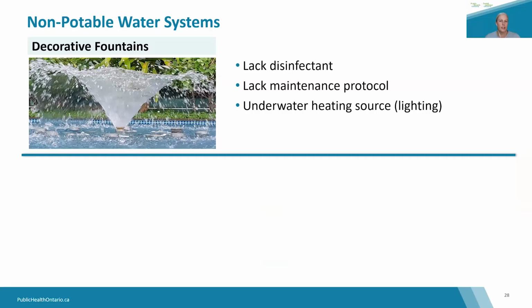So our non-potable water systems are also considered a potential source of Legionella, and these include systems like decorative fountains. There's a number of concerns with decorative fountains. They often lack any type of chemical disinfection. There can be minimal to no maintenance protocols for these systems. They're not regulated in Ontario, so there's no operating requirements.